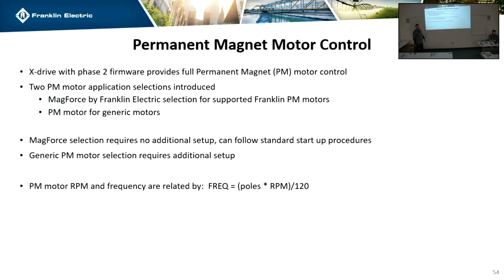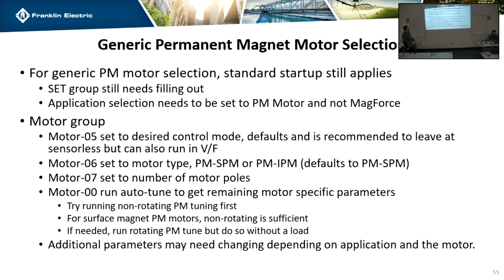So hold on, you guys sell permanent? We have one pump permanent magnet motor. Okay. Submersible, right? Yeah, specific to submersible. Oh, just submersible? Yeah. But regardless of pump or HVAC, if you have a permanent magnet motor, as long as it doesn't require the encoder, some permanent magnet motors have a feedback to the drive that's an encoder signal. We cannot support that yet, so we can't do that. But any other generic permanent magnet motor will work.